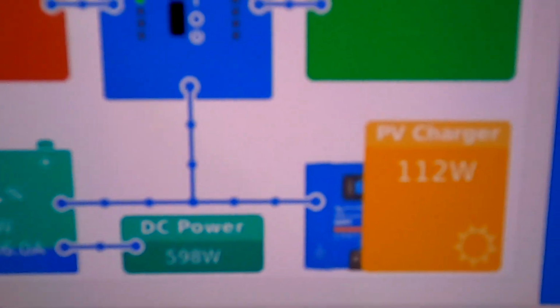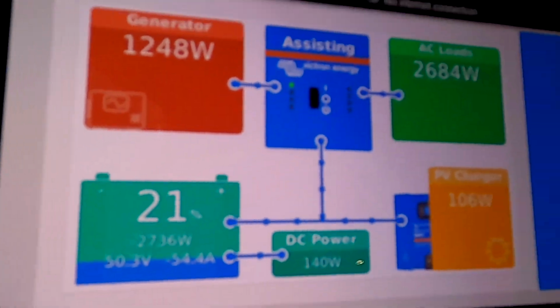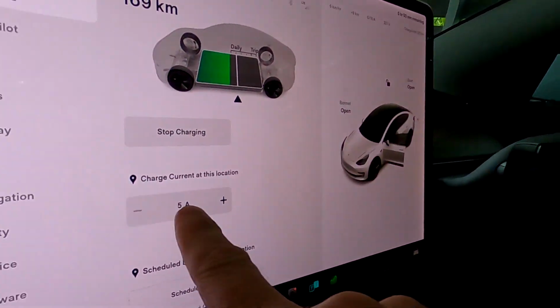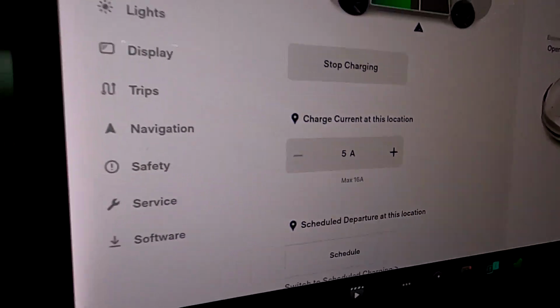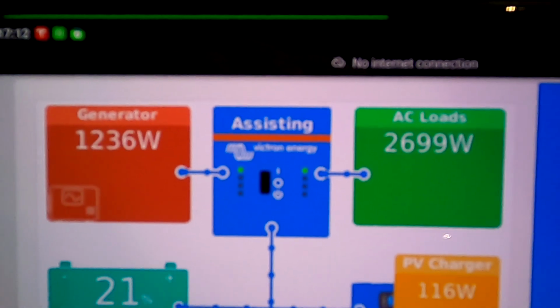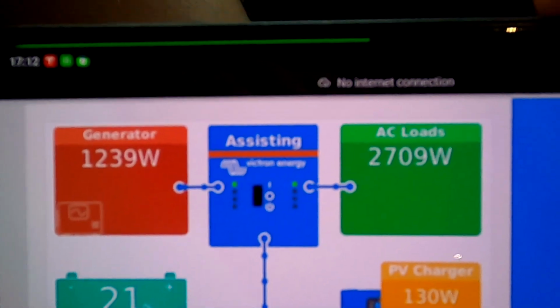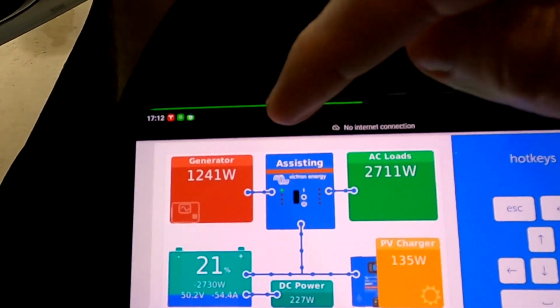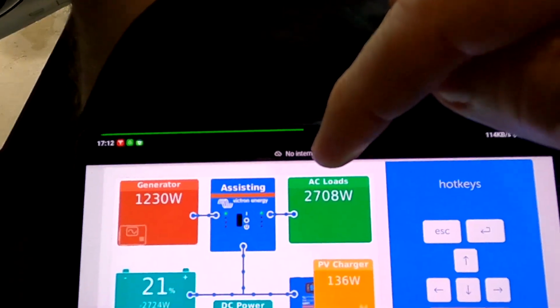I just hope we're not losing here. We need to watch the amps coming from the battery, since solar is only contributing about 100 watts. Remember we've got a 100 amp fuse inside the battery box, and the circuit breaker for the battery is rated at 90 amps - but it should be fine for this test. Right now we're charging at 5 amps, with 16 being the maximum, so we can crank it up more. On screen we can see 1.2 is coming from the Phoenix and the rest from the Multiplus - so this plus 3000 should equal 4.2.